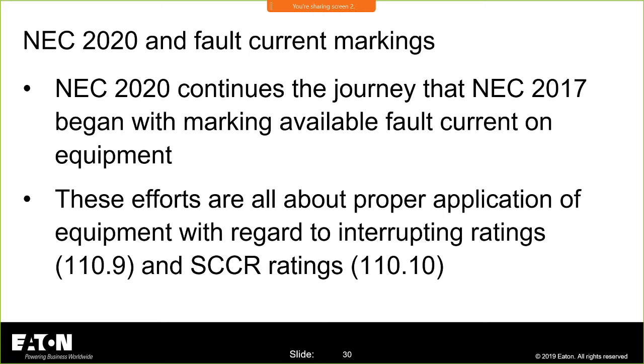Okay, so 408. We had a marking, and I'm going to cover all of the different marking requirements, but we now have to field mark available short circuit current or fault current on all of our panel boards, switchboards, and switchgear. And again, it's all about the proper application of equipment, whether it's 110.9, which is interrupting ratings, and 110.10, which focuses on short circuit current ratings.